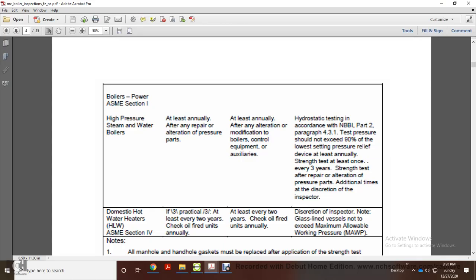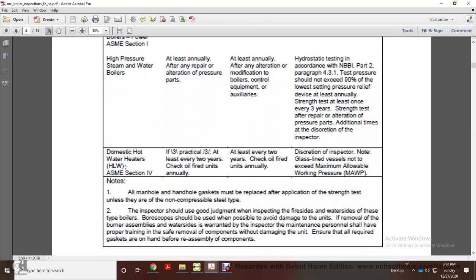strength tested after repair or alteration of pressure parts, and at additional times at the discretion of the inspector. Domestic hot water or HLW boilers, ASME Section 4: if practical, at least every two years, check oil fired units at least every 2 years, check oil fired units annually. Discretion inspection. Note: glass-lined vessels not to exceed maximum allowable pressure.